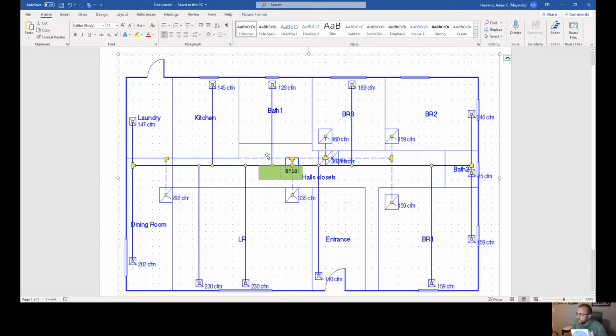All right, so how much did we have going to the left? Well, 50, 100, 100, 100. So we got 1, 2, 3, 4, 5, 50. 550. I know I'm confusing you all. I'm sorry. All right, so 550. I'm going to punch that into my ductulator. I'm going to go to the 0.1, and I'm going to go to 550. What that's going to tell me is how big that first piece of duct after the main piece has to be to carry that whole end.